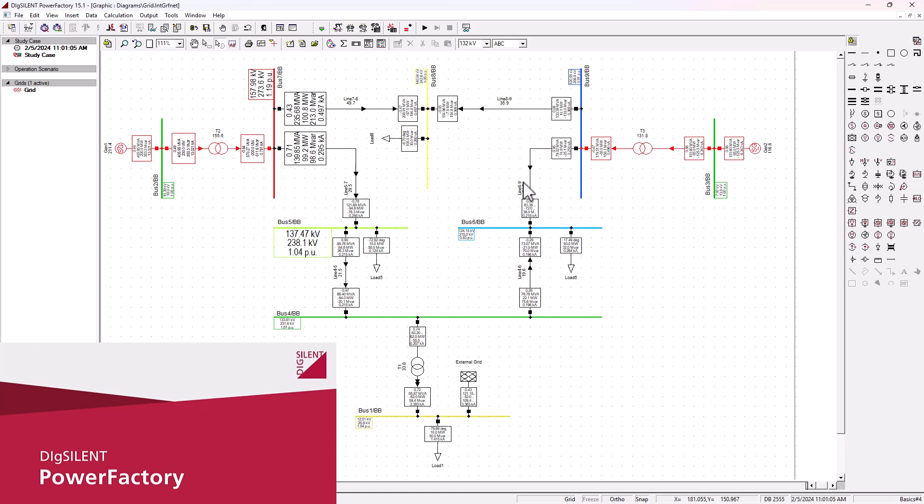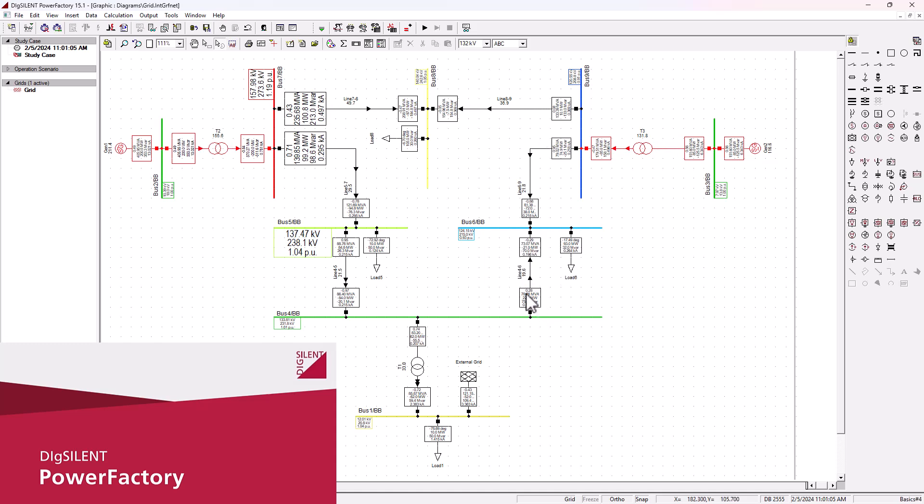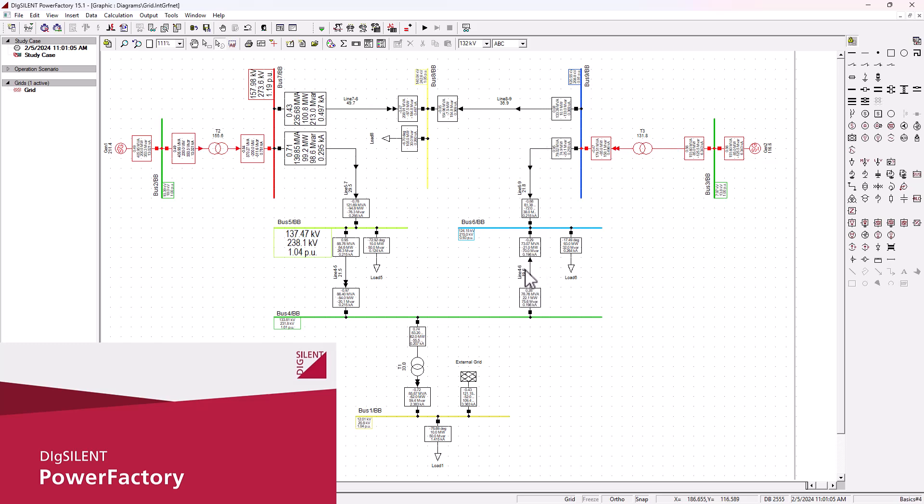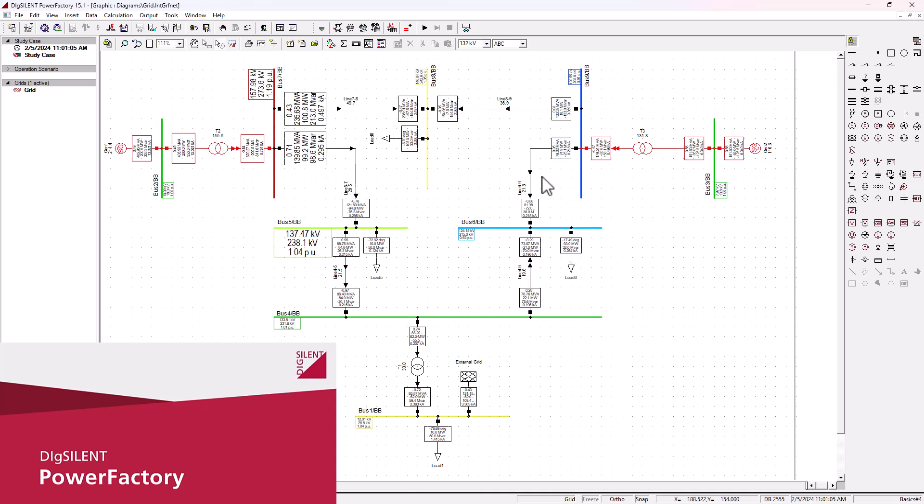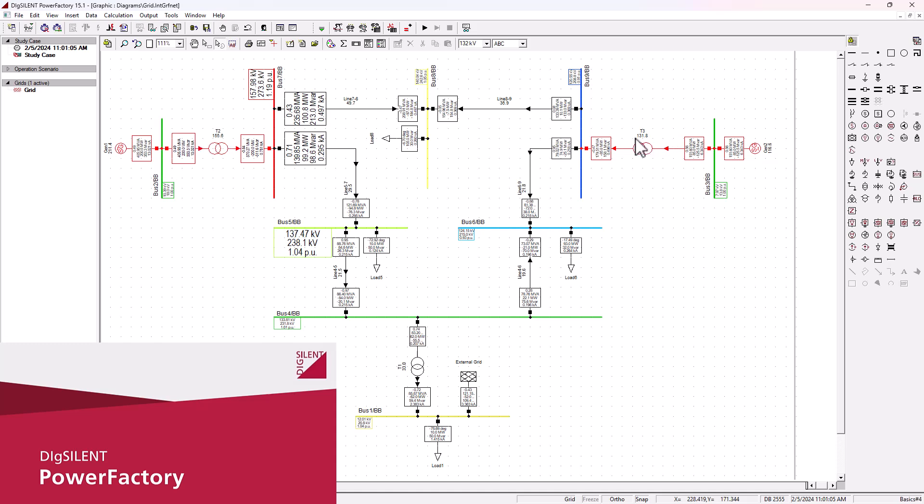Now if we put line 6 to 9 out of service, that would mean to continue to supply 93 megawatts, there must be an increase of power on line 4 to 6. You have to ensure under this condition line 4 to 6 is still able to supply more power to compensate for a line that's just been put out of service. Obviously that situation will be beneficial for this transformer T3 because it will reduce the loading on it.